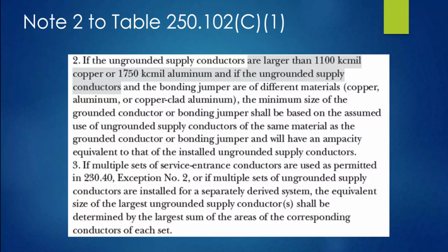Right, where it might be, for example, a 250 aluminum, the equivalent to it would be, if you did that equation, I'm just using this as an example, probably a 3-aught copper. That would be equivalent to the 250 aluminum. Now, again, this only applies to those over 1100 and 1750, but I'm just using that as an example of how you would do that using the ampacity. Okay, I did that 3 times, so hopefully I got that right, and I won't get a bunch of hate mail saying I got that wrong, but that's how you do it.